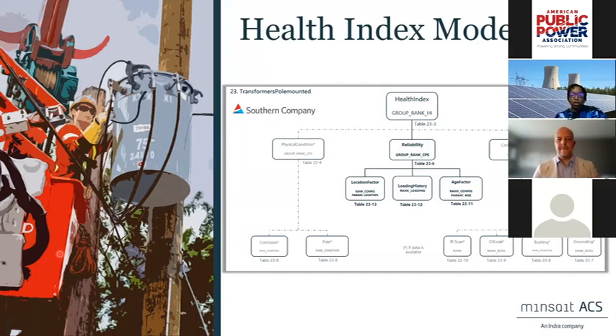We don't really track those inspections in the system, as well as the connection insulation, IR scans, oil leaks, bushings, groundings. There is no set maintenance program for overhead transformers to look at each of those qualities and make a judgment on that. So we only focused on the reliability, because that was all the information we had readily available.